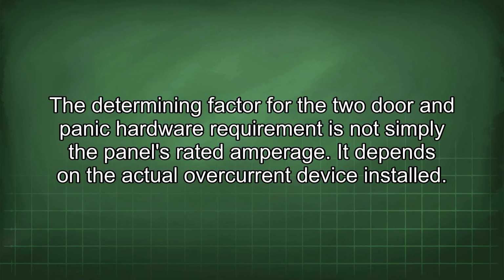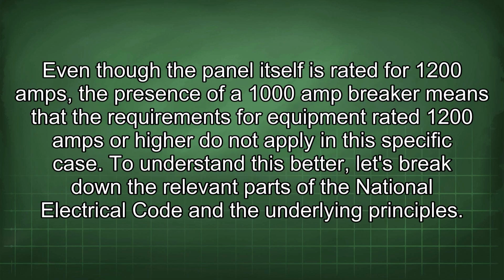The determining factor for the two-door and panic hardware requirement is not simply the panel's rated amperage. It depends on the actual overcurrent device installed. Even though the panel itself is rated for 1200 amps, the presence of a 1000 amp breaker means that the requirements for equipment rated 1200 amps or higher do not apply in this specific case.